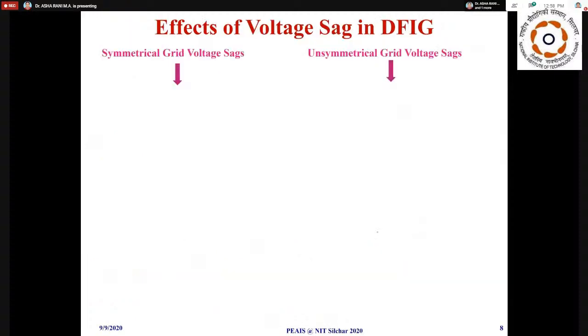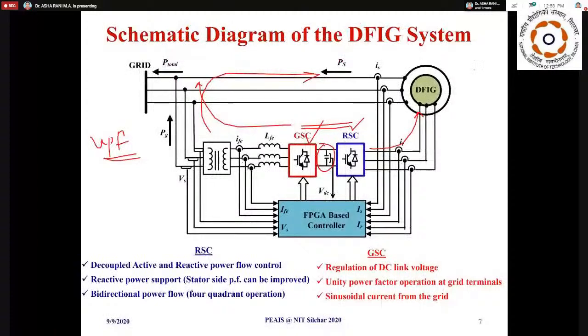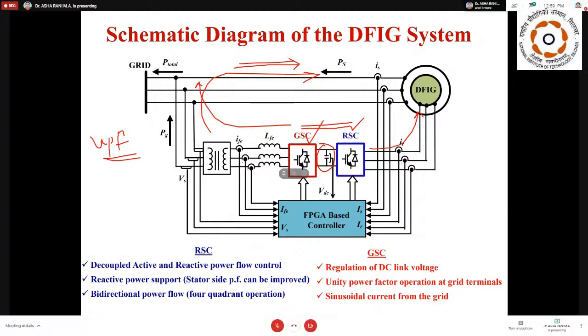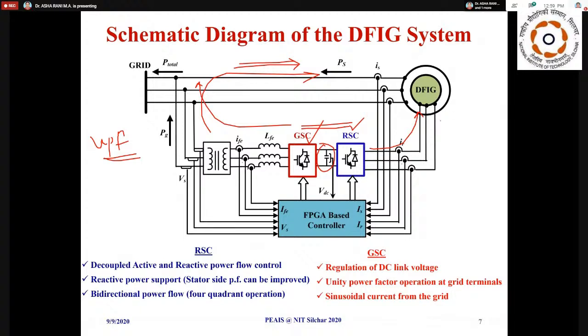We are talking about unity power factor operation at grid terminals, and also maintaining sinusoidal current in the grid. So even though we are telling a lot of things like this, the major disadvantage of DFIG is that it is very sensitive to unbalance. Let us assume there is an unbalance of 10% in the grid. Even a very small unbalance causes huge unbalanced current to flow through the stator. These currents go directly to the machine. Since the stator and rotor are magnetically coupled through the air gap, this huge stator current will have a major impact on the rotor. It will increase the rotor voltage enormously, and huge rotor currents will flow.